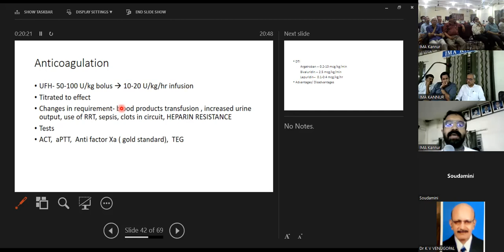That is the ACT. We monitor the ACT every 4th hour. We keep it around 160 to 180 seconds. The ACT itself has problems sometimes, and we monitor the APTT also, because the APTT takes time for the result and it's a much costlier test, whereas the ACT is a point of care test. So we correlate between the APTT and ACT, and we continue monitoring with the ACT. And if there's any variation in the ACT, we monitor the APTT. There'll be changes in the heparin requirement based on blood product transfusion, use of renal replacement therapy, sepsis, clots in the circuit, heparin resistance. The tests used for monitoring are basically ACT, APTT. The gold standard is anti-factor Xa, and then TEG.